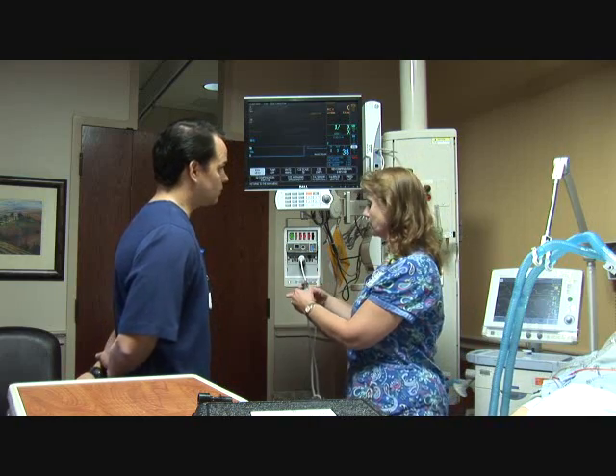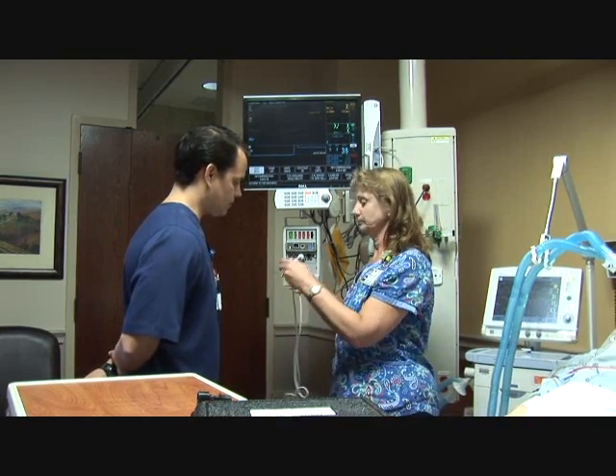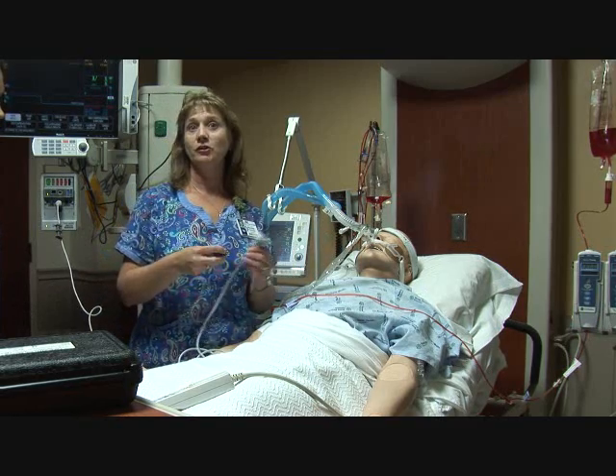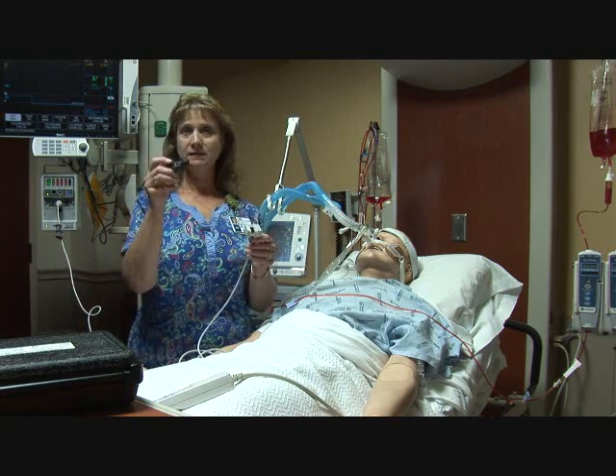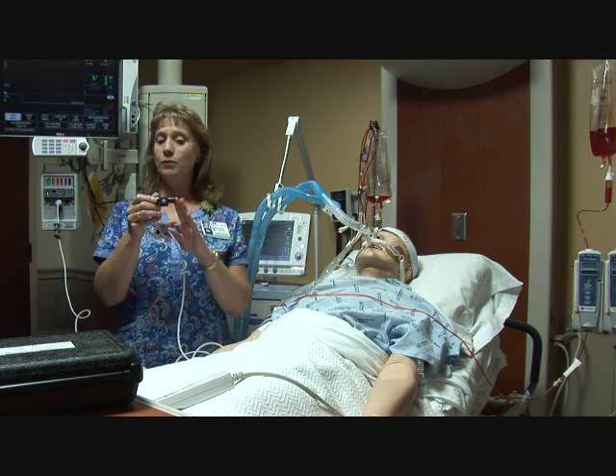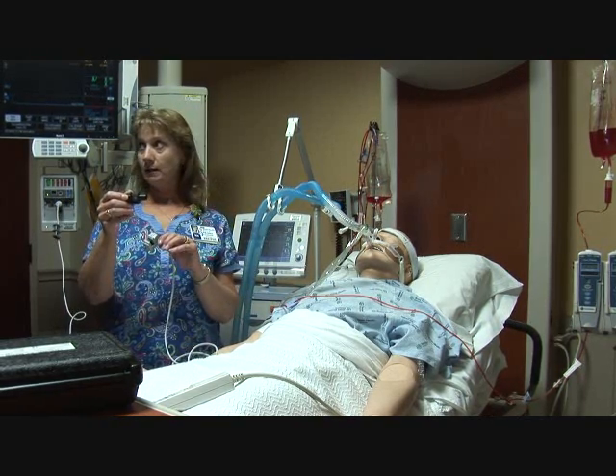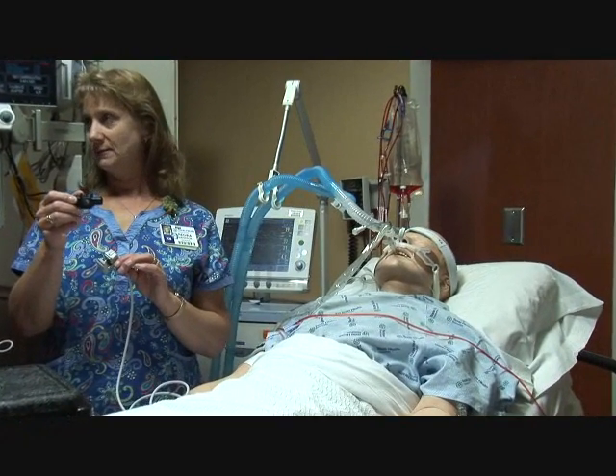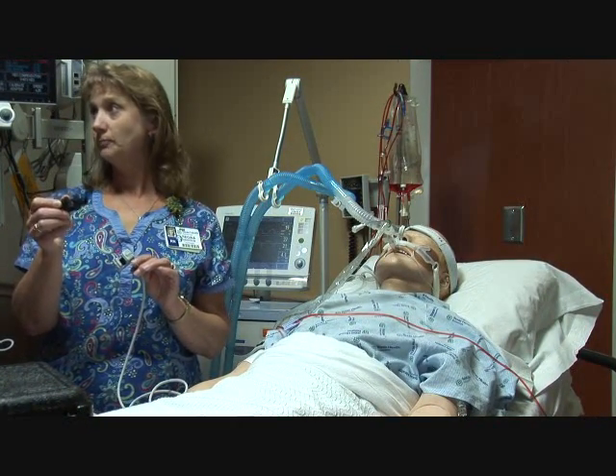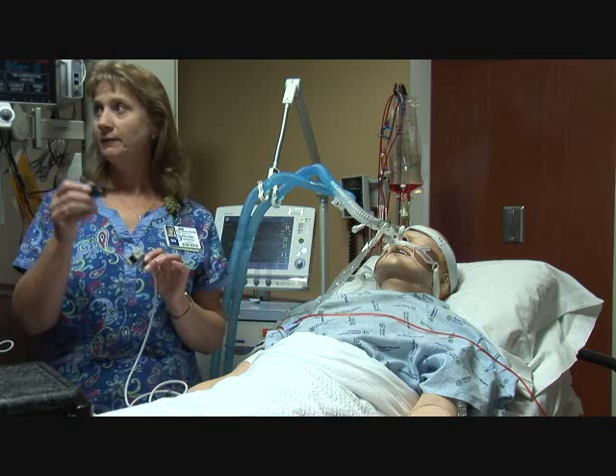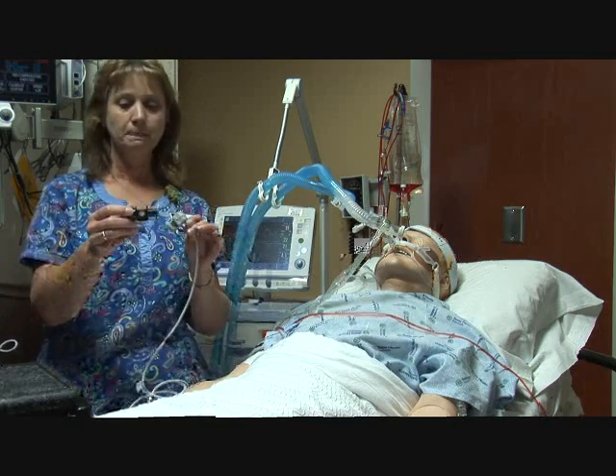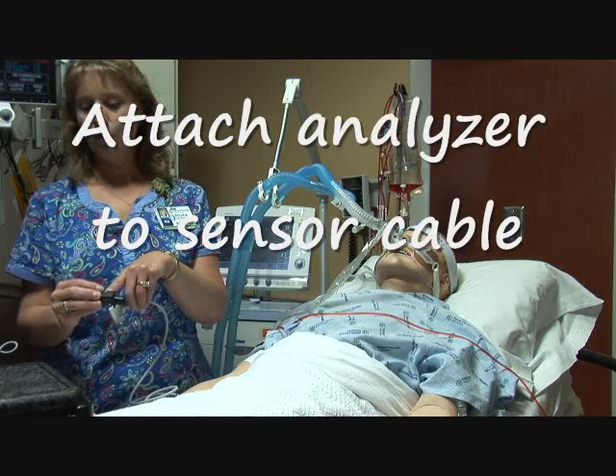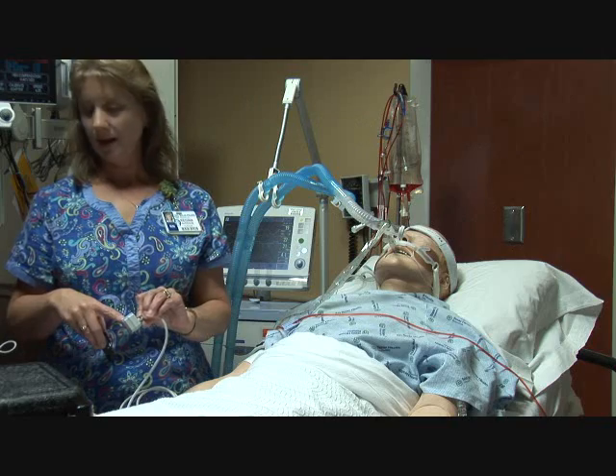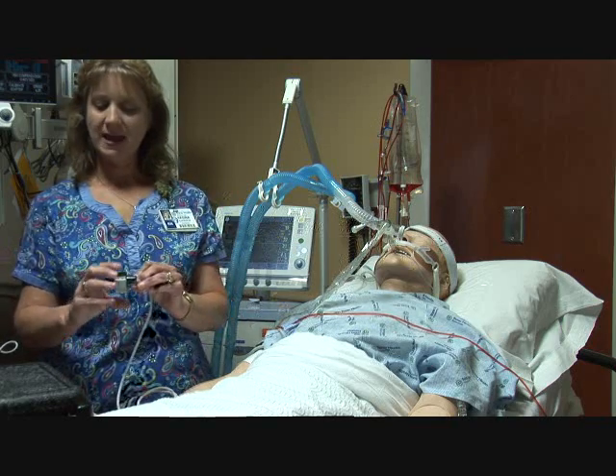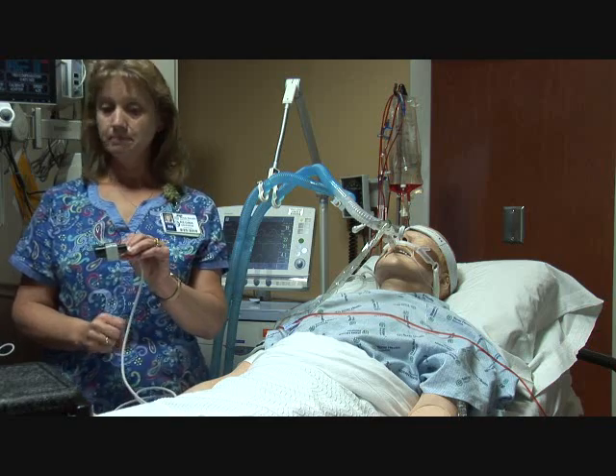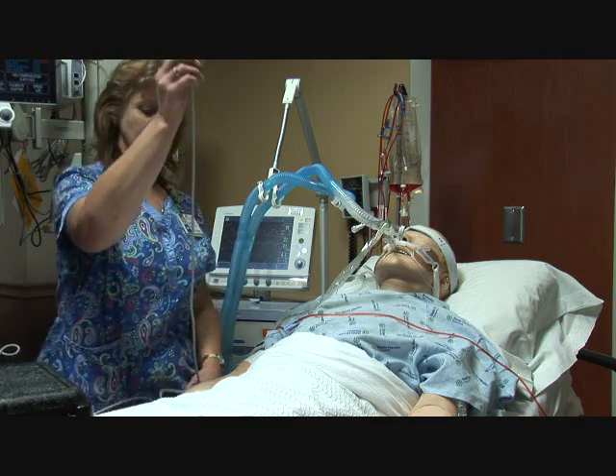Okay, so you're going to take this off. You're going to take your analyzer adapter. There are two different types. The black one is a permanent adapter, and then there are clear ones that are disposable. We've got the permanent one, so we'll have to properly wash that when we get done. But you take this, and there's a white arrow here, and then there's a white arrow here. Okay, so you would just snap that in. Okay, and then we're going to get ready to attach it to the patient.